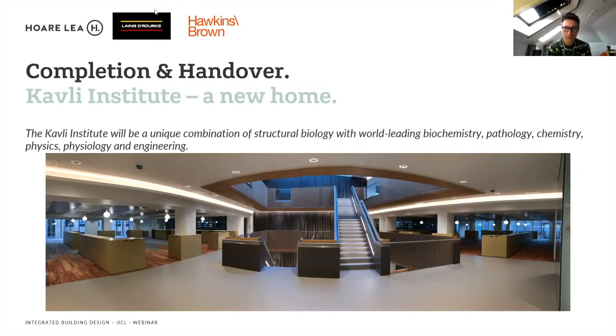Do you want to go at that one, Shane? I can have a crack at the second part, the environmental control strategy within phase 2. In principle the broad strokes are similar. If we take a typical lab space, heating and cooling is managed via LTHW and chilled water plant, then fan coil units at high level concealed within the ceiling void in each area. Air changes in the labs were circa 6 air changes an hour as a baseline, similar to phase 1, but how that air is derived uses central air handling unit plant, set up in a different way.